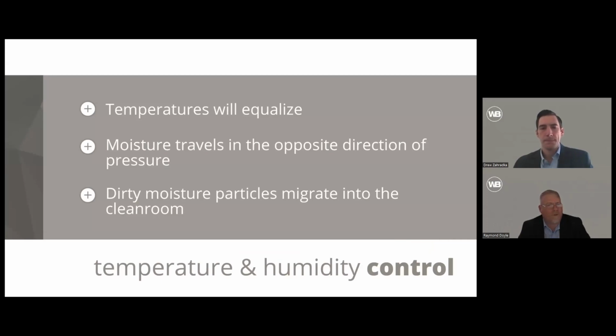So one of the things that is often misunderstood in clean rooms and in pressurized spaces in general, but it does cause problems in clean rooms, is the fact that moisture does travel in the opposite direction from pressure. We call it moisture migration, but it's basically a state of equalizing pressures or gas pressures inside of the air. So if you have more moisture outside of the space than you do inside the space, the moisture will migrate on air particles and through the air in the opposite direction of pressure.